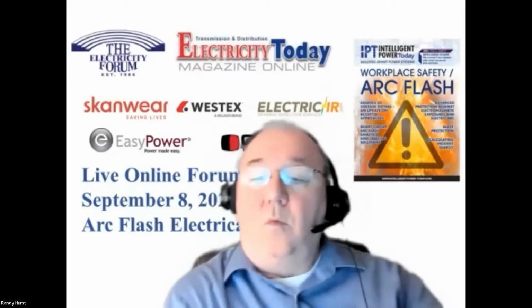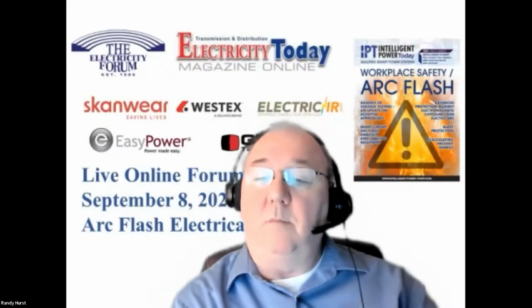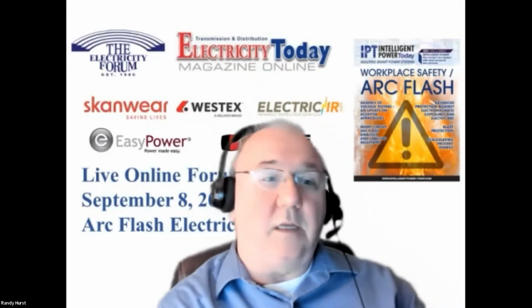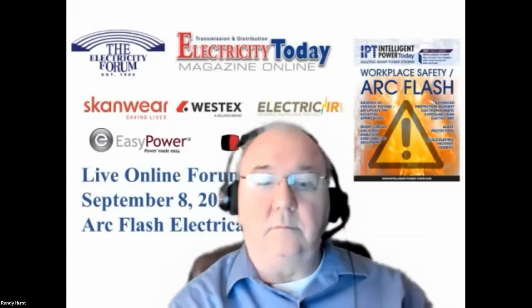First up, will the clothing be designed to minimize hot metals sticking into it? So all Arc Flash clothing, as part of the test of Arc Flash clothing, is obviously tested in an Arc Flash situation. So you saw the two garments that were in an Arc Flash test. The Arc Flash itself will create the heat. You'll then also get the molten metal. So any Arc Flash clothing is designed to withstand molten metal as a result of an Arc Flash.